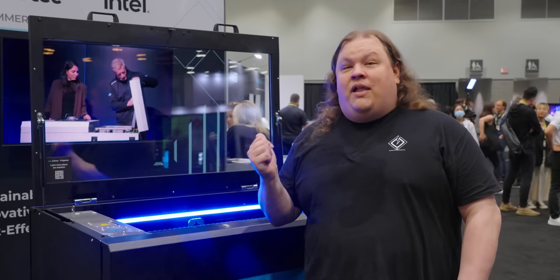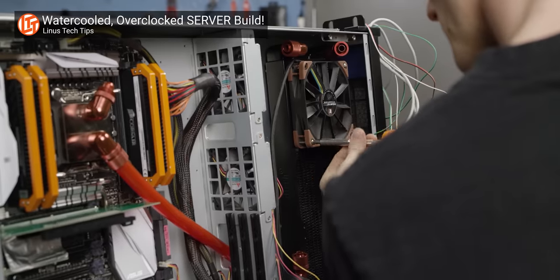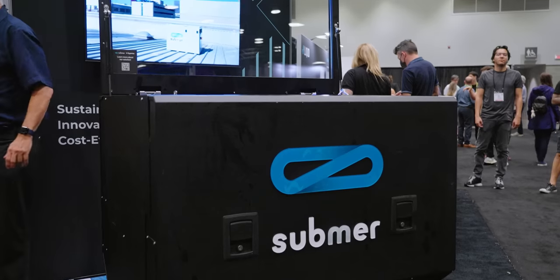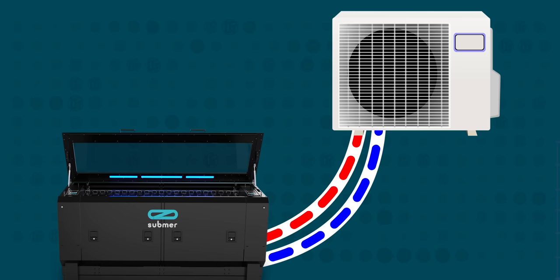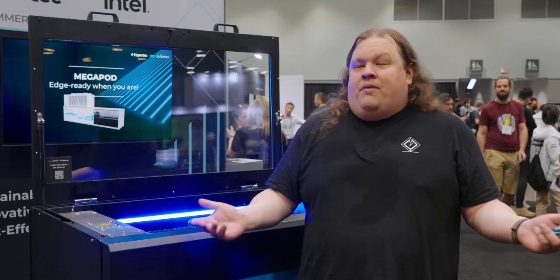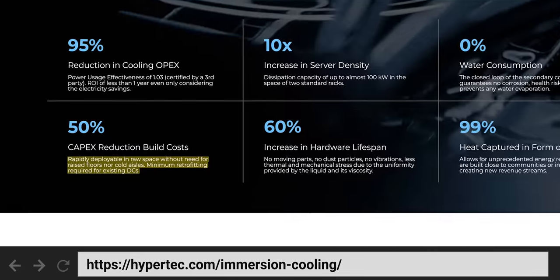They're also making the chassis out of ocean recycled plastics by end of year, at least that's what they hope to do. Server racks in data centers are already cooled by high-end air coolers and even liquid coolers, so why are we even talking about this? Well, this rack has zero fans and is basically silent by comparison. It works by pumping the coolant through a loop to an exterior box that looks a bit like an HVAC unit. That box exchanges the thermal energy from the hot mixture to a cold water source in a single-phase arrangement, meaning practically all of the noise — so the pump basically — ends up well outside of the room.